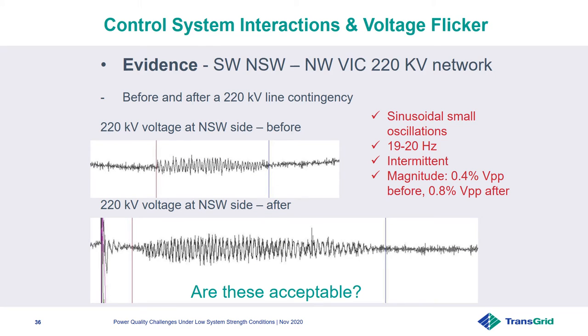An example is given here. This is a recording from a network event where a line in the network was tripped. The recording shows small sinusoidal oscillations before and after the event. These oscillations are at 19 to 20 Hz modulation frequency, seem to be intermittent, and the magnitude of these oscillations as seen at the New South Wales site is 0.4% voltage peak to peak before the event and 0.8% voltage peak to peak after the event. So we all have a question: are these acceptable?